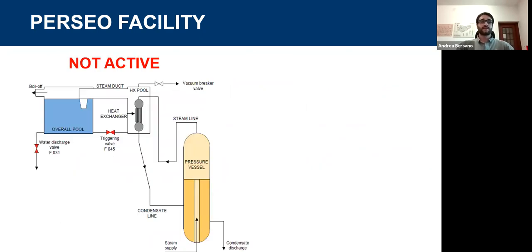This is a sketch of the PERSEO facility when not in operation, connected to the primary side. When the system is not active, the valve connecting the two pools is closed, so there is no water in the pool where the emergency heat exchanger is located. Therefore, heat transfer from the emergency heat exchanger to the pool is negligible because there is only air.